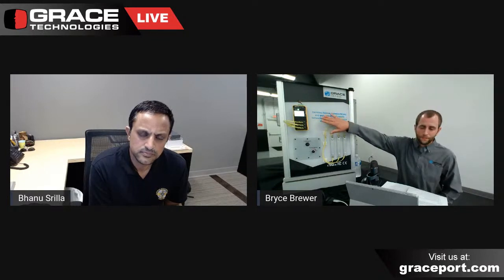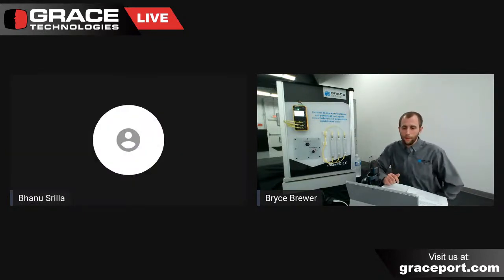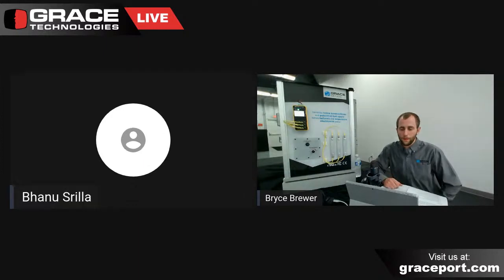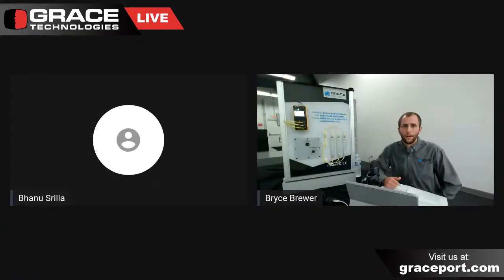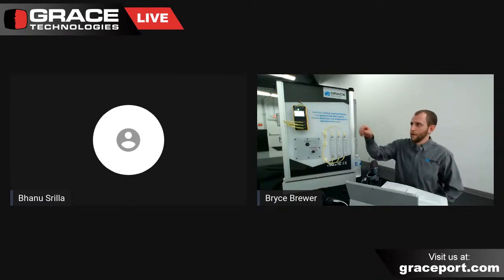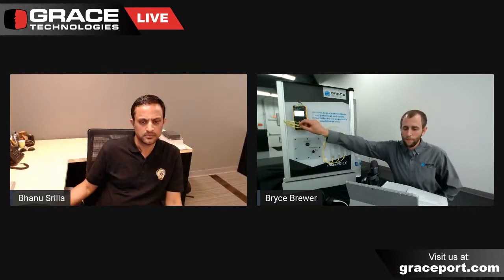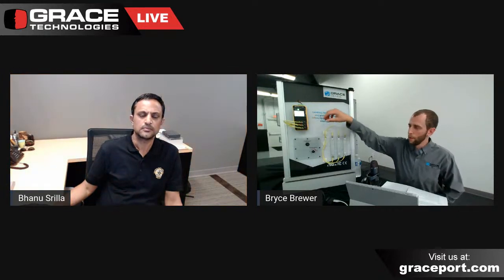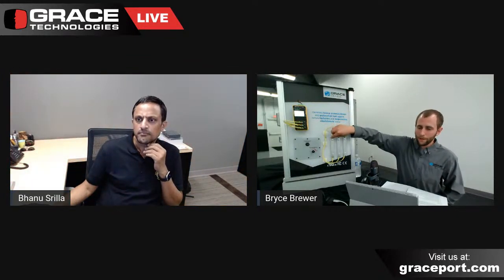So what we came up with is the hotspot monitor you see right here. This would sit in your low voltage compartment on your switchgear, MCCs, or anything like that, and then we route out these fibers. These yellow ones are optical fibers that go out, and you can bolt them onto your connections. We're zoomed out here, but basically you take this fiber, it goes onto a ring lug, and you can bolt it onto any connection you're interested in.